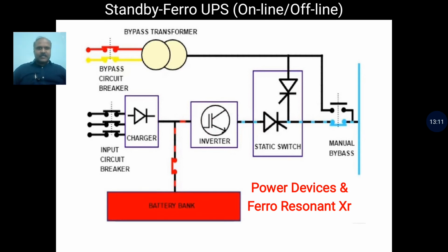In this case, the charger circuit consists of power electronics like a regular rectifier or a controlled rectifier, nothing but thyristors, can be considered. The inverter is generally made up of IGBTs, as well as a static switch, nothing but a semiconductor thyristorized switch, for switching from load to mains line or load to inversion action. The red block shows the battery bank, which charges whenever mains is present and delivers DC power to the inverter for inversion whenever AC mains cuts off.